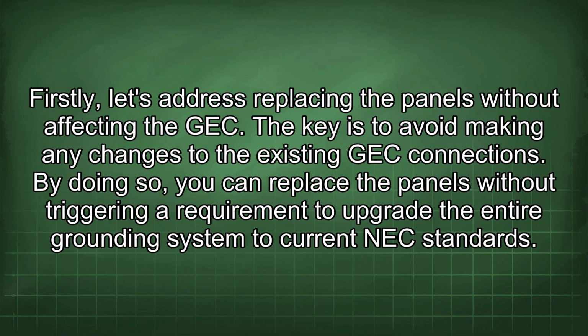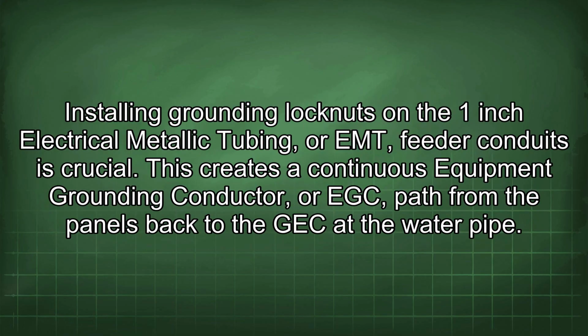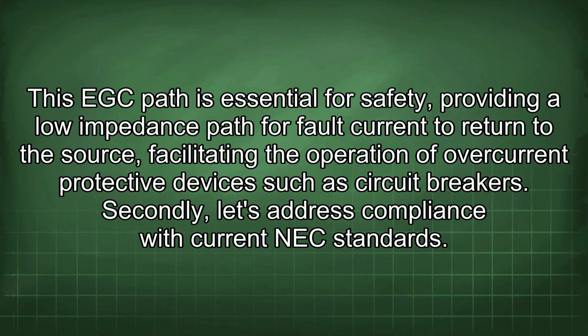Firstly, let's address replacing the panels without affecting the GEC. The key is to avoid making any changes to the existing GEC connections. By doing so, you can replace the panels without triggering a requirement to upgrade the entire grounding system to current NEC standards. Installing grounding lock nuts and the 1-inch Electrical Metallic Tubing, or EMT, feeder conduits is crucial. This creates a continuous equipment grounding conductor, or EGC, path from the panels back to the GEC at the water pipe. This EGC path is essential for safety, providing a low impedance path for fault current to return to the source, facilitating the operation of overcurrent protective devices such as circuit breakers.